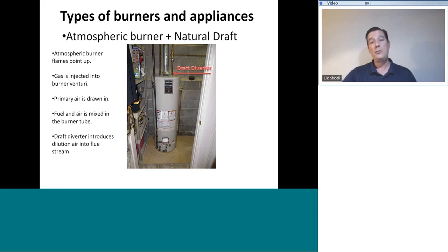and that is pretty normal. What you want to watch out for, especially on water heater draft diverters, is rust on the top of the heater and around that draft diverter area. What that tells you is you have been chronically failing to allow flue products out, and instead they are trying to come out of the draft diverter. They're spilling down and billowing around and touching the top of the water heater where they condense their flue products into moisture badly enough and often enough to rust out the top of the water heater. So rust on the top of the water heater is often an indication of a poor draft.